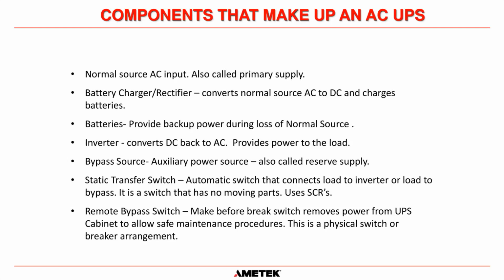The static transfer switch is an automatic switch that connects the load to inverter or the load to bypass. And it is a switch that has no moving parts. It actually uses SCRs, which are silicon controlled rectifiers. They're semiconductor devices. You send a signal to them and they turn on instantaneously with no moving parts in them. So they're very robust and very reliable.